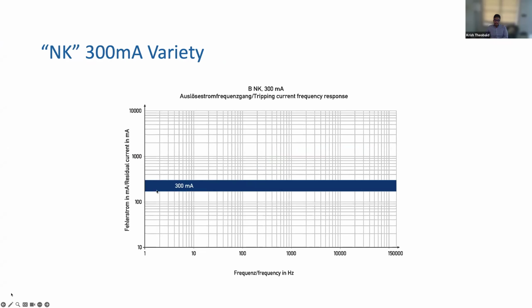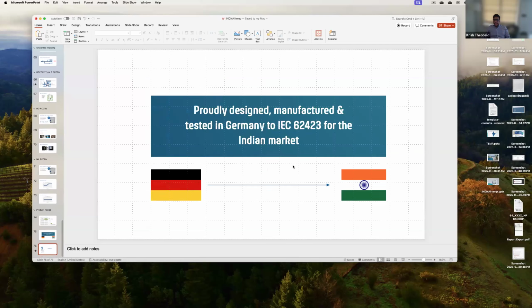But like he said, there are certain types available where regardless of the frequency, it trips. Now, if you have a type AC or type A RCD here, a type AC or type A RCD cannot trip correctly in the presence of harmonic current. So you need a type F for single phase applications, if composite residual currents exist, so harmonics and fundamental frequency, which will be most cases, and for 3-phase, type B.